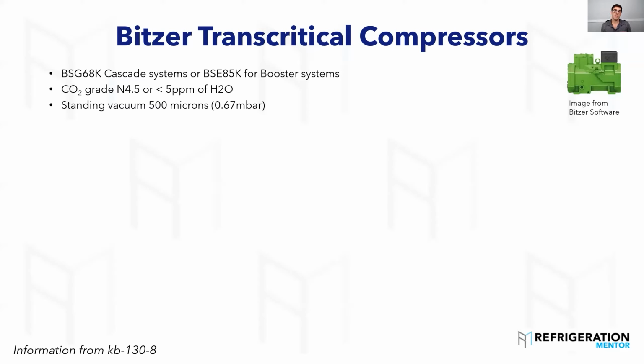A lot of the time, if you read in the manual, the KB130 here, they'll say they want you to charge through a filter if you can't have Coleman grade. There's other ones that say you can use lower grades depending on the OEM manufacturer. I always say the more dry refrigerant, the better, because moisture is really, really bad in the system, because it causes copper plating, causes acid, causes a lot of different things.